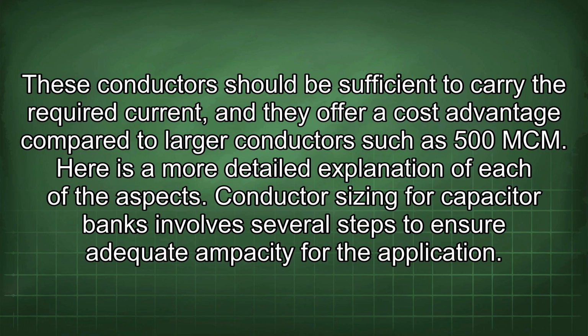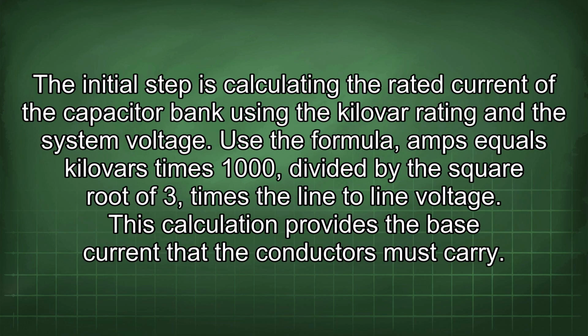Conductor sizing for capacitor banks involves several steps to ensure adequate ampacity for the application. The initial step is calculating the rated current of the capacitor bank using the kilovar rating and the system voltage. Use the formula amps equals kilovars times 1000 divided by the square root of 3 times the line-to-line voltage. This calculation provides the base current that the conductors must carry.